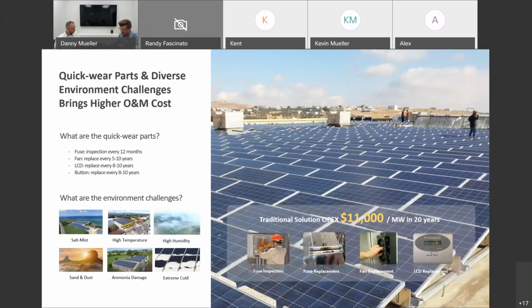Fans typically, if you have a higher quality EBM PAPST, for example, they're typically rated between 40 and 80,000 hours of runtime. And that sounds great, but that runtime is under ideal conditions, typically in a lab. If you put that inverter in an environment, on a farm, on a roof, for example, in a Canadian climate specifically, where you have fairly high temperatures in the summer and extremely low temperatures in the winter, that's not going to help and increase the longevity of that fan. So for most systems, within the first 10 years, there's definitely one fan replacement. And most other companies who do have fans actually have fan brackets available to change the fan easier. But if you don't even have a fan, that topic is completely off the list, and you don't have to worry about any cooling issues based on failed fans and things like that.